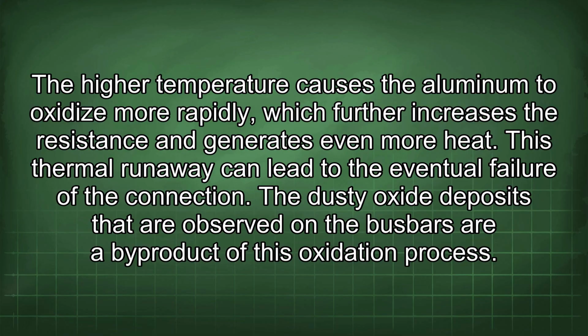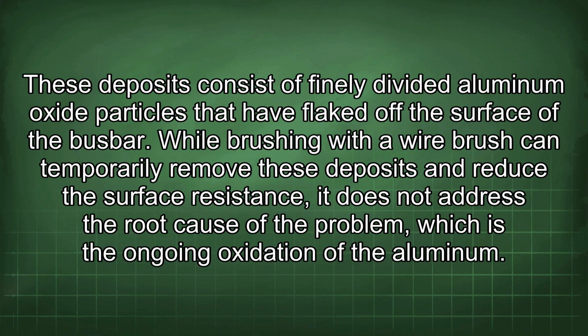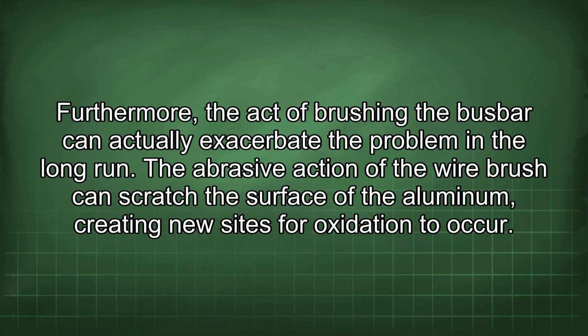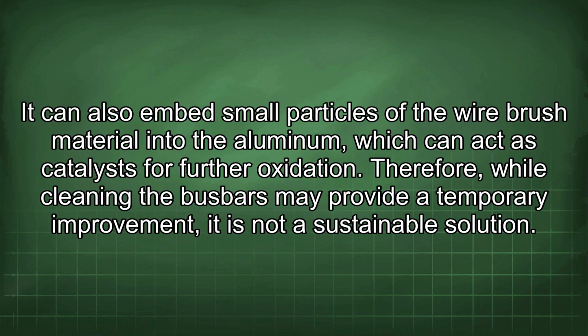The dusty oxide deposits that are observed on the busbars are a byproduct of this oxidation process. These deposits consist of finely divided aluminum oxide particles that have flaked off the surface of the busbar. While brushing with a wire brush can temporarily remove these deposits and reduce the surface resistance, it does not address the root cause of the problem, which is the ongoing oxidation of the aluminum. Furthermore, the act of brushing the busbar can actually exacerbate the problem in the long run. The abrasive action of the wire brush can scratch the surface of the aluminum, creating new sites for oxidation to occur. It can also embed small particles of the wire brush material into the aluminum, which can act as catalysts for further oxidation. Therefore, while cleaning the busbars may provide a temporary improvement, it is not a sustainable solution.